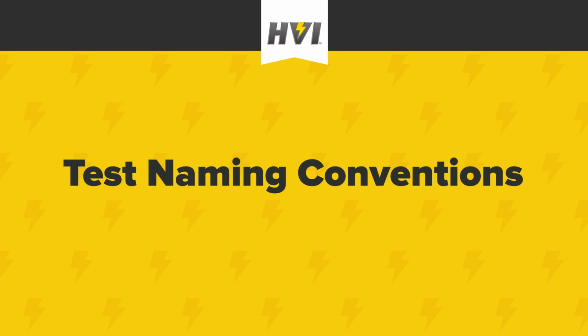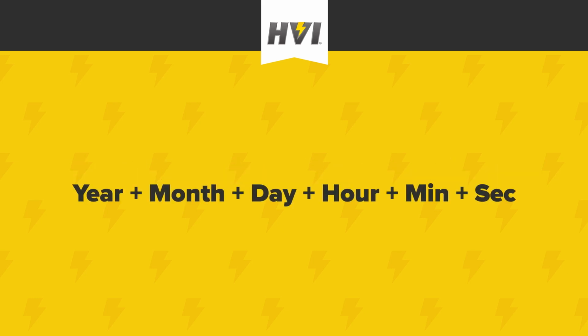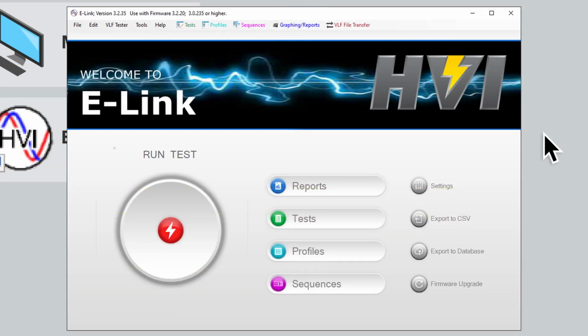E-Link software uses a standardized file naming convention based on the date and time, and names all saved tests along this convention, until a user renames them with a name of their own choosing. Default file names are year plus month plus day plus hour plus minute plus second, and end in a .hvc file extension. For example, the name of a test run on the 1st of January 2022 at 2:30 p.m. would be 2022-01-01-14-30-00 hipot.hvc.